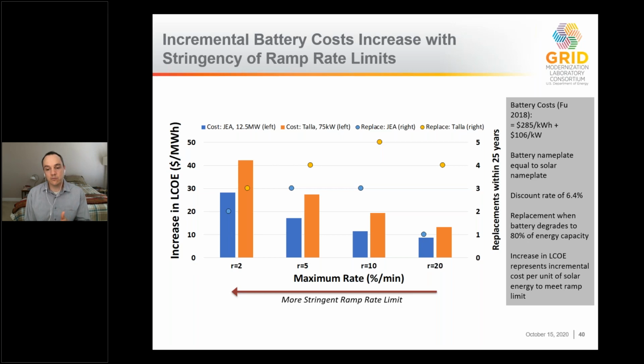What that meant was that in order to meet that higher, or more stringent, ramp rate limit, you would increase the initial cost of this. And if we look at what the cost would be per megawatt hour of solar generation, we estimated that using the battery to do the smoothing function would range from about $10 per megawatt hour to $40 a megawatt hour of additional costs, depending on the degree of smoothing that you're requiring.